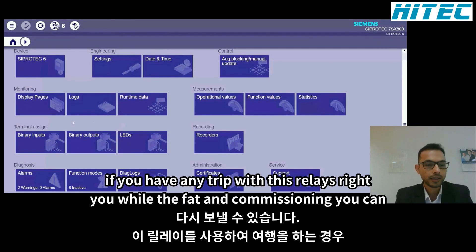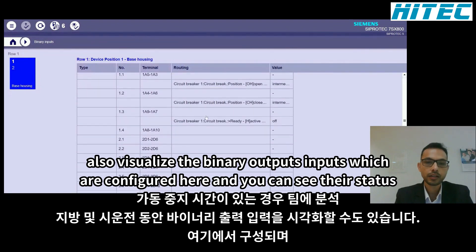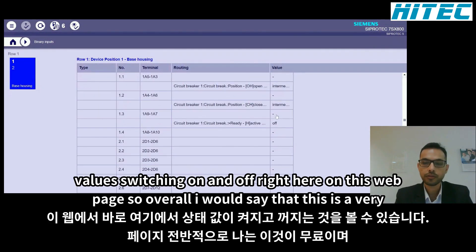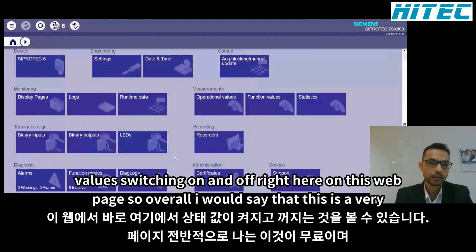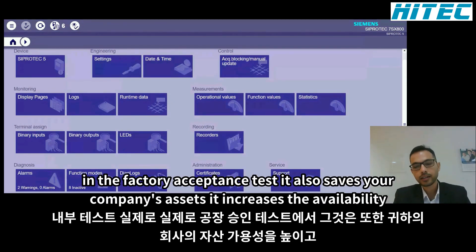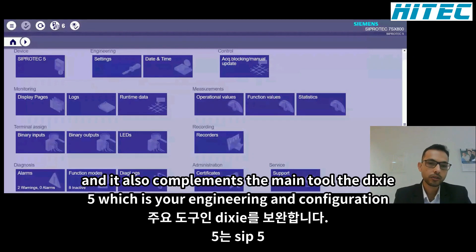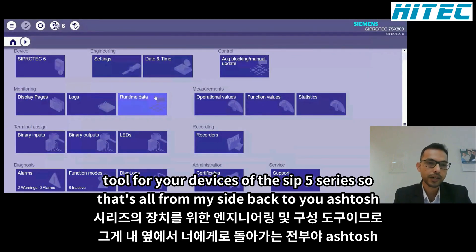During FAT and commissioning you can also visualize binary outputs and inputs and see their status — switching on and off — right on this web page. Overall, this is a very versatile, free tool with many use cases in site testing and factory acceptance testing. It saves company assets, increases availability, and complements the main tool, DIGSI 5, which is the engineering and configuration tool for the SIPROTEC 5 series.